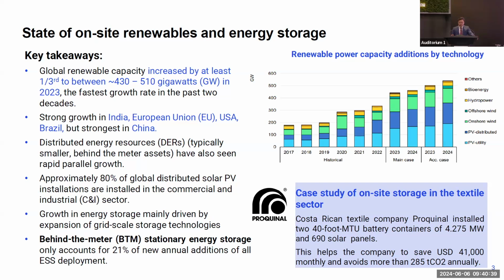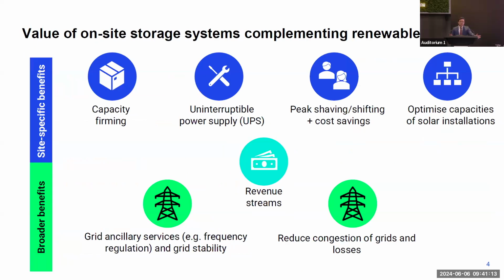However, we identified one case study where this has been deployed: at a Costa Rican headquarters, two 40-foot MTU battery containers with a combined storage capacity of 4.275 megawatts were installed alongside 690 solar panels over a covered parking lot, with a generation capacity of about 0.255 megawatt peak. This allows the facility to save $41,000 every month by arbitraging low tariffs at night against higher tariffs in the day, and has avoided close to 300 tons of CO2 equivalent emissions annually. So what is the value of on-site energy storage?